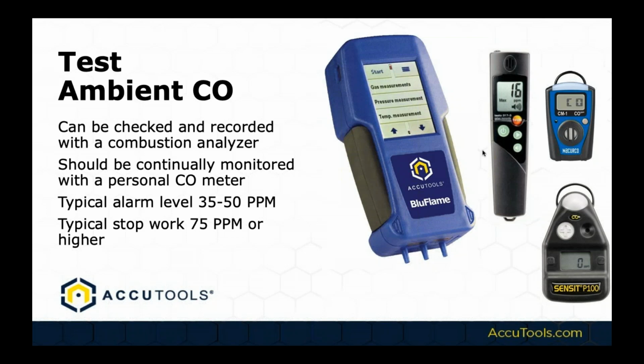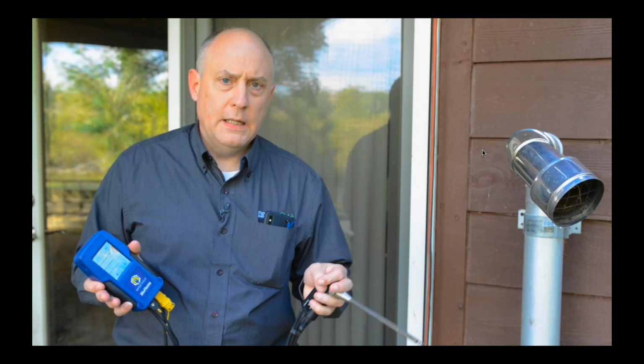Because you've got to remember, when testing, you're in a dynamic environment. Things are always changing. You're running and stopping fans. You're turning on and off burners. There are other burners in a room, maybe a hot water tank or a dryer, or in a boiler room there could be other boilers. Just because what you're working on isn't contaminating the environment doesn't mean something else locally can't be. So you should always monitor your CO level, and we highly recommend you carry an ambient CO meter.